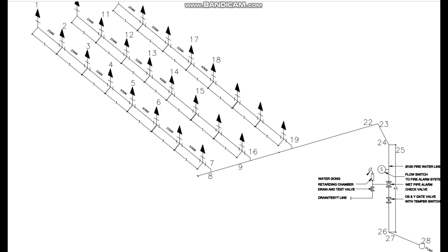Good morning friends. In this hydraulic calculation video, we are going to size a fire pump for a high-rise building. The building consists of basement plus ground floor plus 13 storeys, with a height of 43 meters. This is the isometric drawing given for the building, which consists of all the sprinklers, alarm check valves, and zone control valve assemblies. We will do the hydraulic calculation from the sprinklers all the way to the pump and decide the pump size.